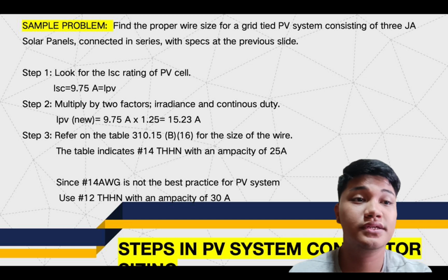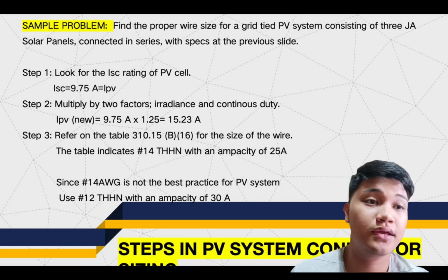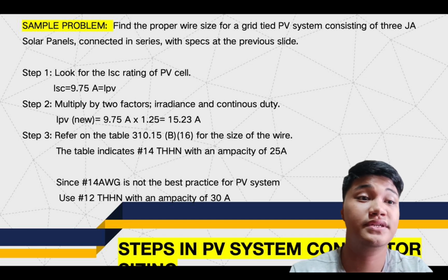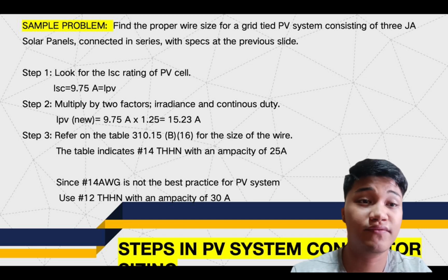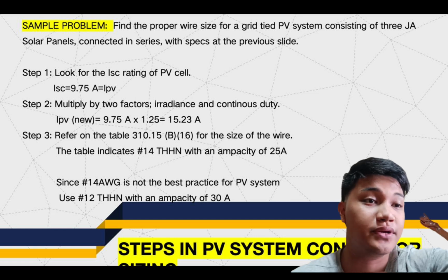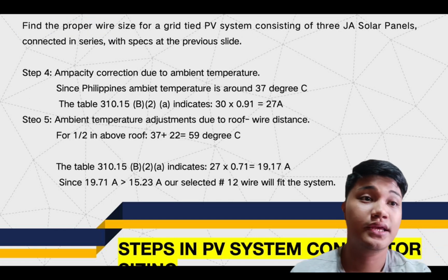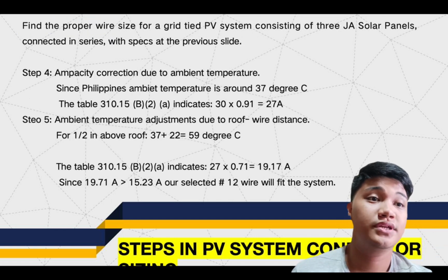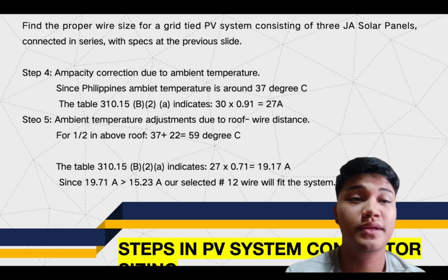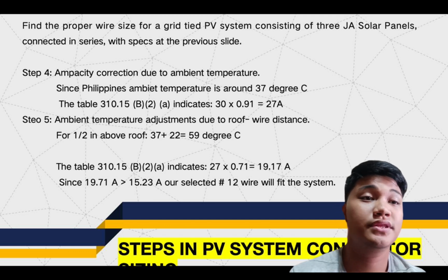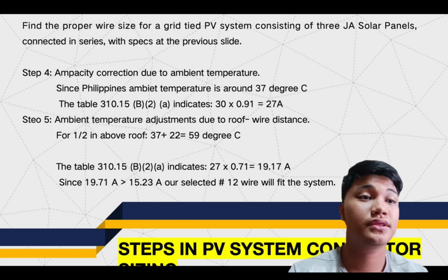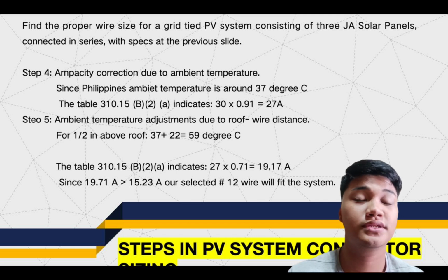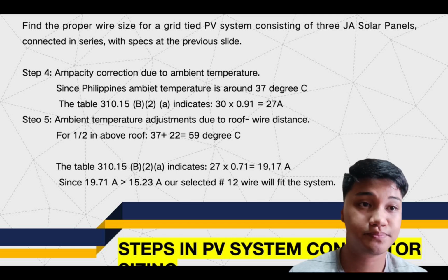Pero makikita din natin na since yung number 14 AWG is not the best practice for PV system, kaya ang gagamitin natin is yung number 12 THHN with ampacity of 30 amperes. Ngayon, ang step 4 natin, ampacity correction due to ambient temperature. So, alam naman natin na yung Pilipinas is nasa temperature ng around 37 degrees Celsius. Makikita natin sa table 310.15 na ini-indicate doon na 30 times 0.91 is equals to 27 amperes.